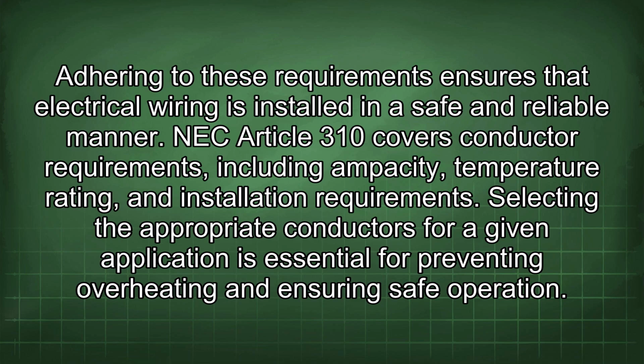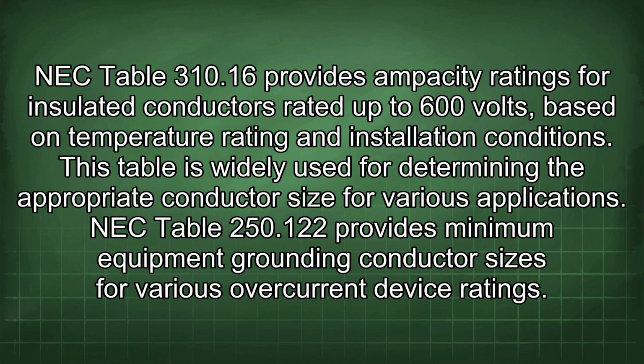NEC Article 310 covers conductor requirements, including ampacity, temperature rating, and installation requirements. Selecting the appropriate conductors for a given application is essential for preventing overheating and ensuring safe operation. NEC Table 310.16 provides ampacity ratings for insulated conductors rated up to 600 volts, based on temperature rating and installation conditions. This table is widely used for determining the appropriate conductor size for various applications.